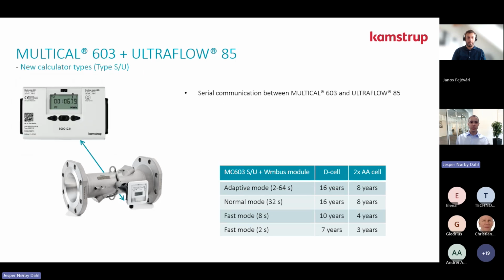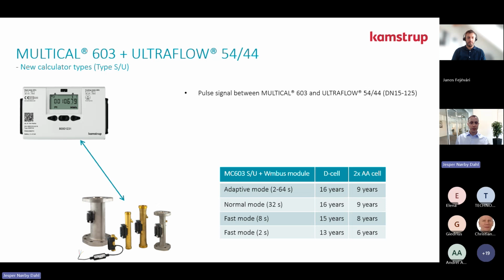If you connect ULTRAFLOW 85 with one of the new PCB types, so the S or the U, then you will have the serial communication. So here you will have the fast update speed, and you will also get a little bit higher battery lifetime. If you connect the new PCB S or U to one of our smaller ULTRAFLOW, so ULTRAFLOW 54/44 from DN15 to 125, then it will work as pulses again as we know today, and you will still have the battery lifetime as we have today with the 16 years.